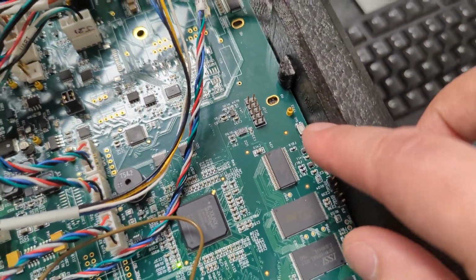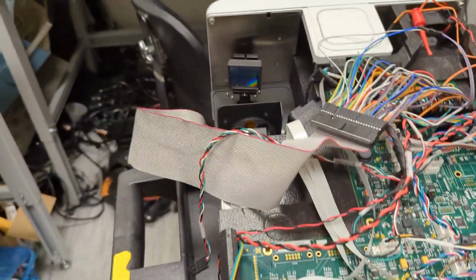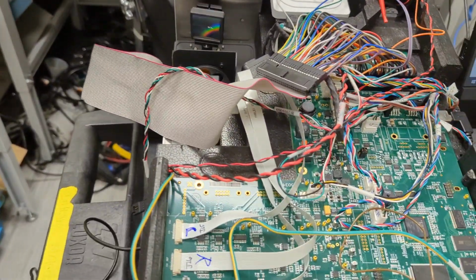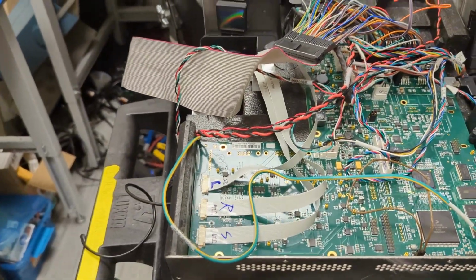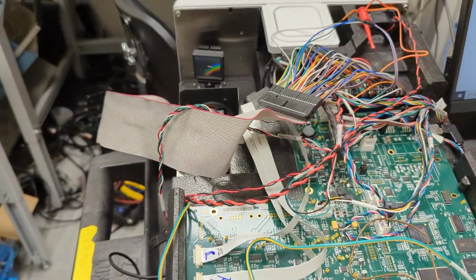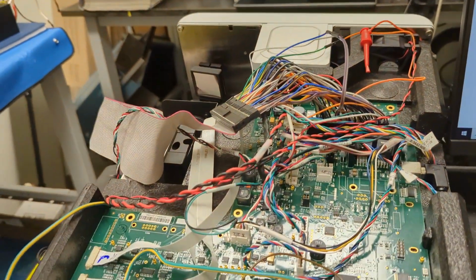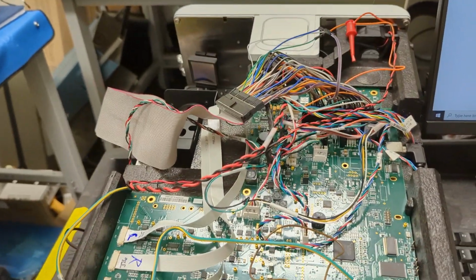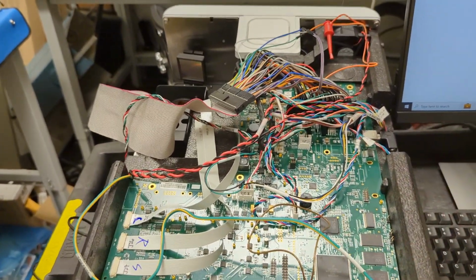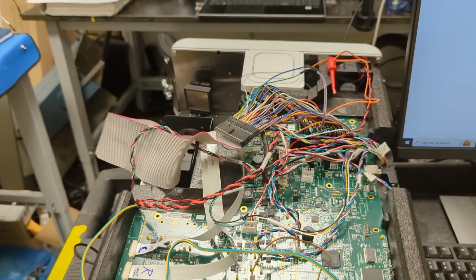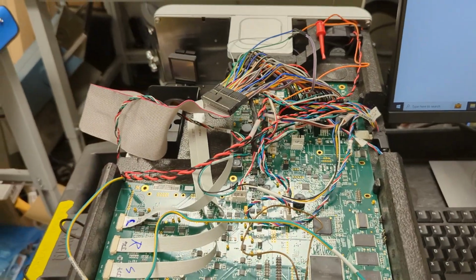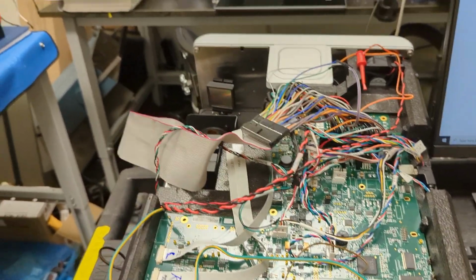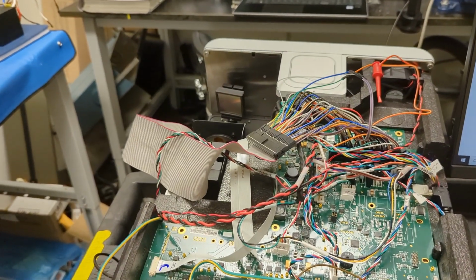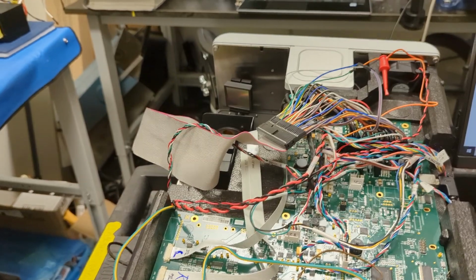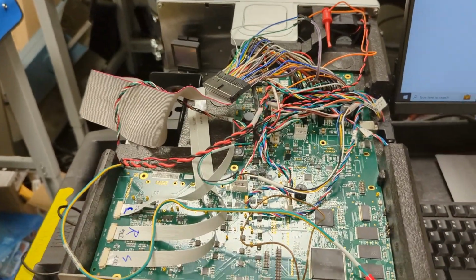Another thing that would come in handy is this button here. It's switch number 1. By pressing that, it will automatically start the instrument's power on self test. So instead of power cycling it and waiting for a bit, you can just do that, because you're going to have to be doing that a lot to get this correct. I'm starting to lose track of where I was. So yeah, that's just a few different things, some details on how you can align one of these. Let me turn the lights off, and I'll show you it going through its startup procedure, and then I can give you guys a bit more details, and then we'll wrap up. I won't keep this going too long.